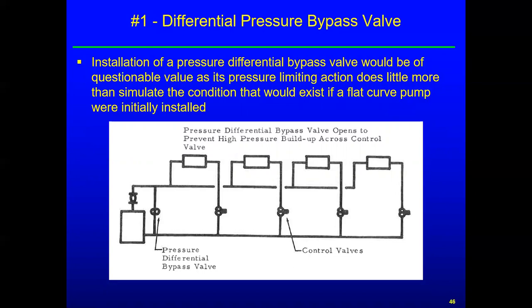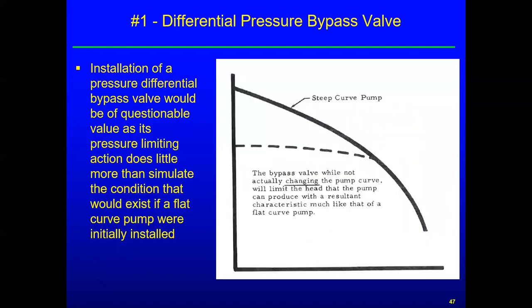And so the author of this, Bell and Gossett, is not a big fan of this. Effectively it flattens out the pump curve, as we'll see on the next slide. So if you had kind of screwed up and had a steep pump curve, putting in that bypass effectively changes the shape of the pump curve. Well, not actually, but as that bypass starts opening, then you just can't build a lot of pressure, even as the flow rate goes out to the system, it bypasses and relieves the pressure. So that would be wasteful of energy, but it would certainly work to keep from overpressurizing the system.